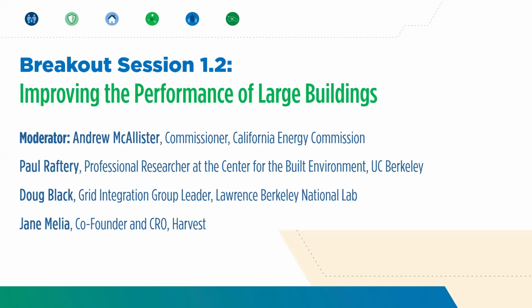You have dedicated on-site staff, but you also have a lot of barriers, and a lot of those are just physical constraints of existing buildings. If you have an existing building that's 50 years old, designed with a traditional chiller and a boiler, you have a big challenge to fully electrify space heating, because the boiler isn't a drag and drop solution. If you want an air source heat pump, you have to physically move the location outdoors, and the equipment is on the order of 10 times larger and heavier, and it adds to electrical capacity.